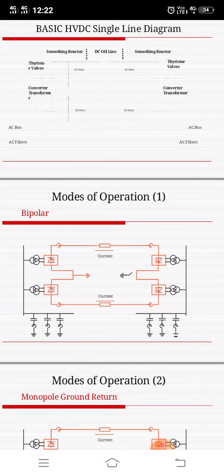More than 50% of the transmission capacity can be utilized, limited by the actual overload capacity of the remaining pole. The advantages of a bipolar solution over two monopoles are reduced cost due to one common return path and lower losses. The main disadvantage is that unavailability of the return path with adjacent components will affect both poles.